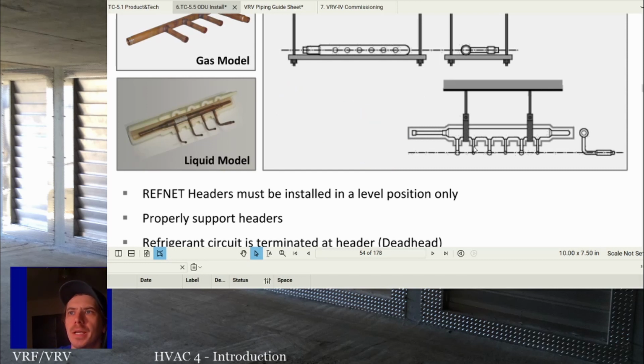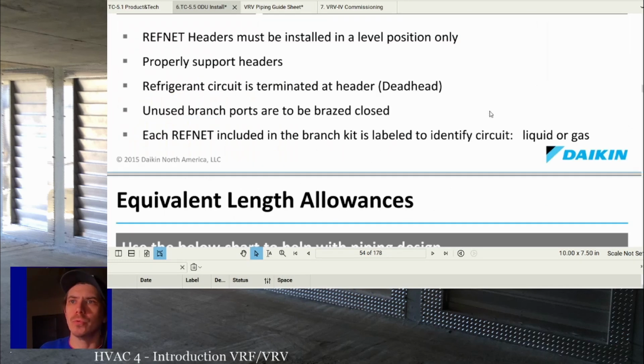All right. Here with the liquid pipe, we even go through an extra effort of making sure that when the water comes in here, and I guess it gets a little confusing here because obviously the liquid's going to favor this one, but because the liquid is going to fill this pipe, it's going to be full of liquid. Since the center line is kind of here where it comes in, all these will fill up evenly. So even if the line is a little bit low on refrigerant, you're still going to have a liquid level that fills up these pipes instead of having a situation where it's not splitting evenly. So anyway, those are the rules. You follow them.